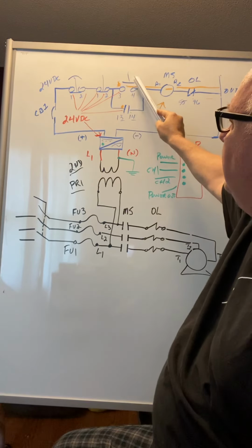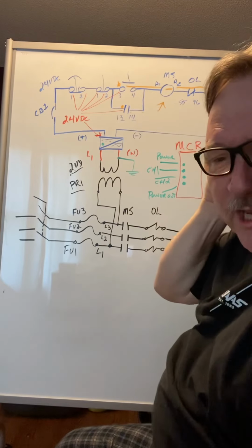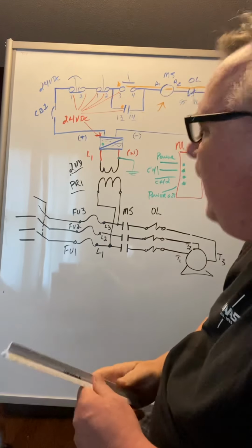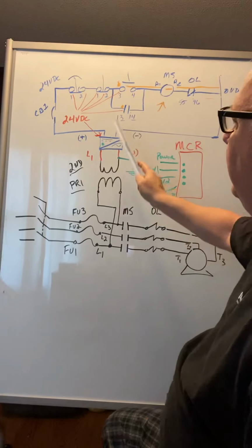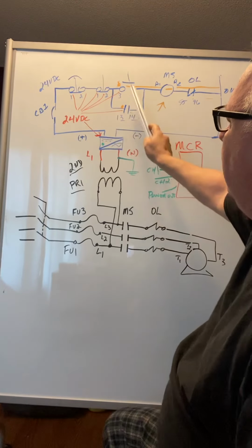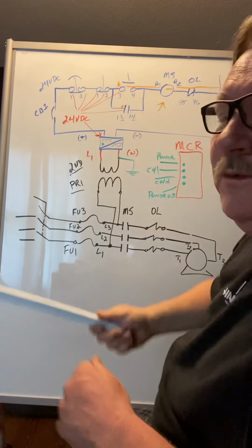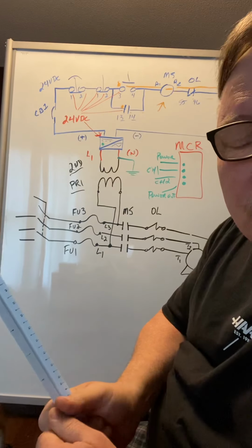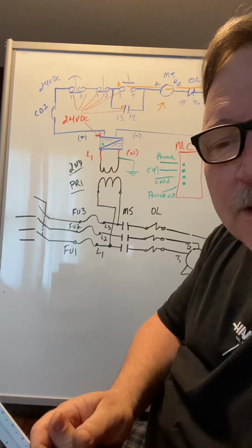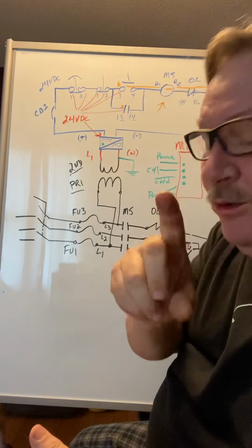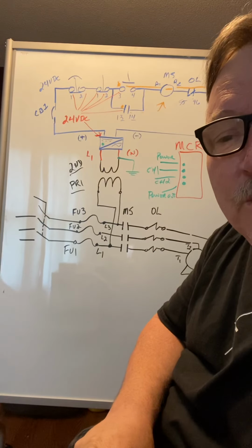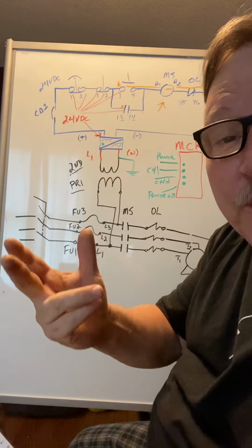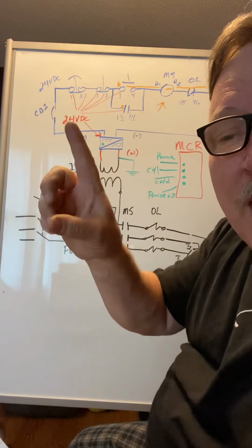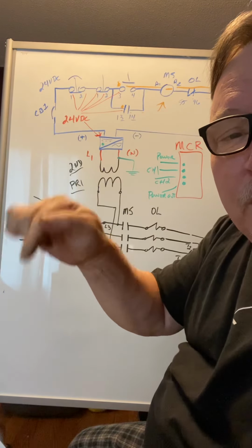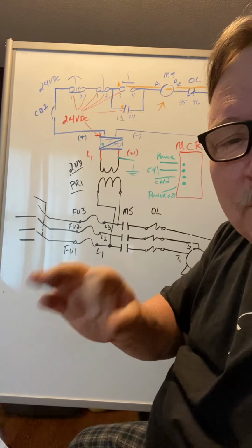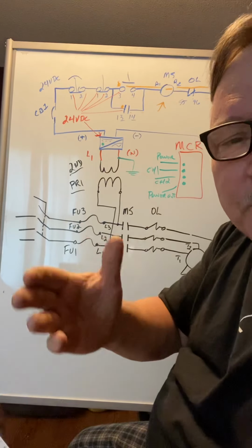To check a power switch with a meter, you're going to make sure you have 24 volts in the system. You will check across this. When you check across an open circuit or an open set of contacts or an open switch, you should see the 24 volts in your meter because it's open. The path is going through your meter. Have your operator press the button, and when he closes it, if that 24 volts doesn't go to 0 or close to 0, you got a switch problem.